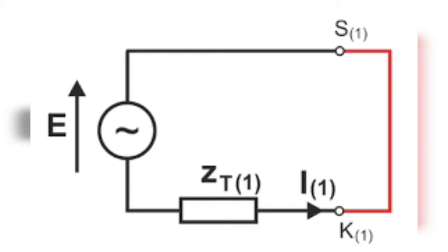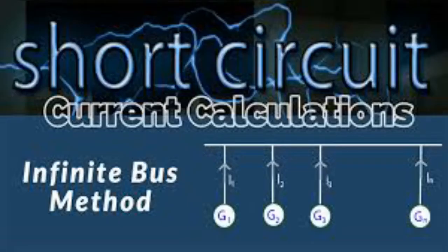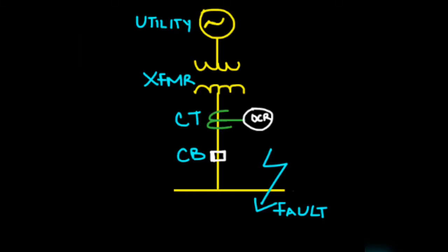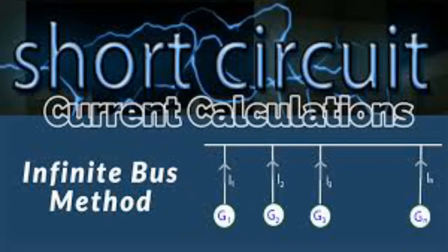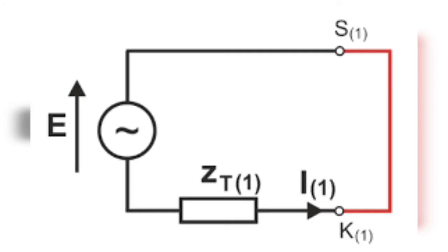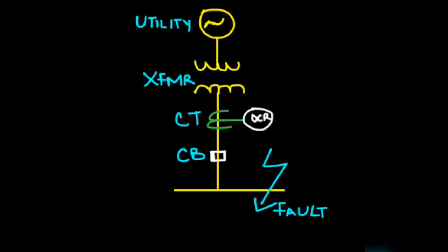How do you calculate the ground fault current? To find the fault current at any point in a network, a sum is made of the impedance in the network between the source of supply, including the source impedance, and the point at which the fault occurred. To find the fault current I k, the nominal applied voltage U divided by the sum impedance Z.